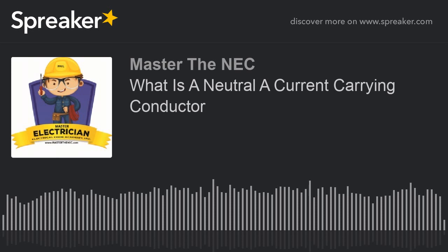So another way that people combat this is they go with what's called a super neutral or an oversized neutral. Whereas they know this is going to happen, they know that neutral conductor is going to carry a lot of current, so sometimes they will double the size of the neutral in an effort to make sure that it can carry a larger amount of current. So if you ever get into an application where you notice that the neutral is larger than the ungrounded conductors, and you do a little looking around, the chances are you're going to see that you're dealing in a situation where you have the harmonics involved in it, okay, and that's what's taking place.